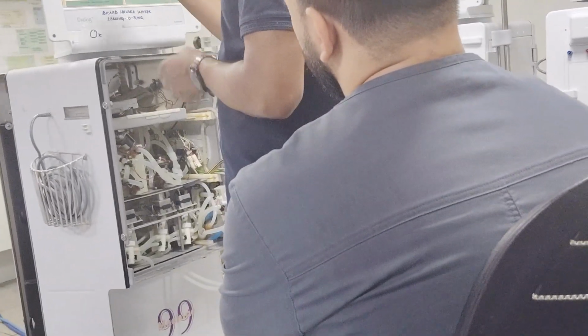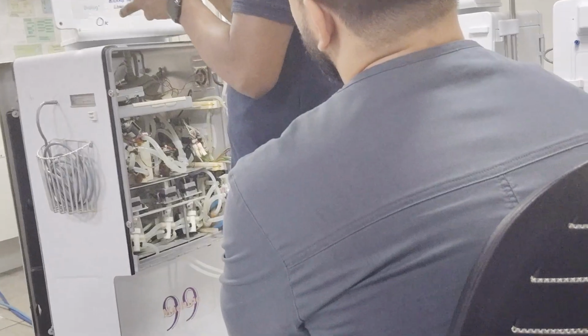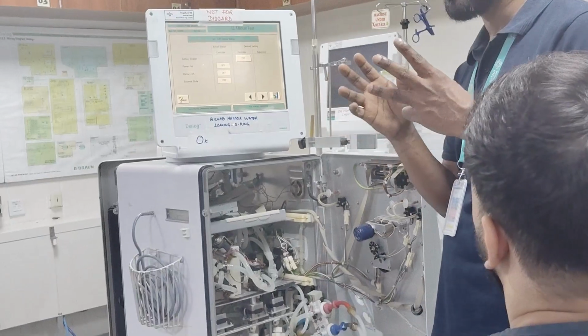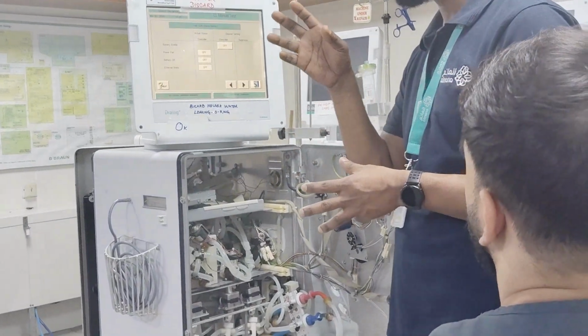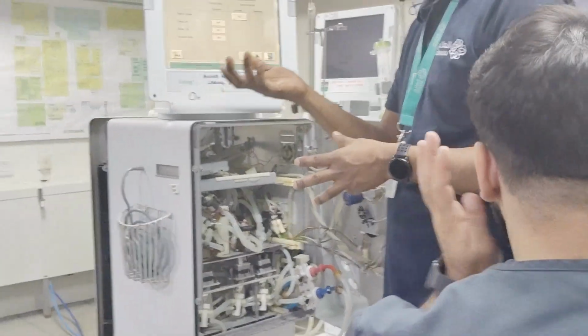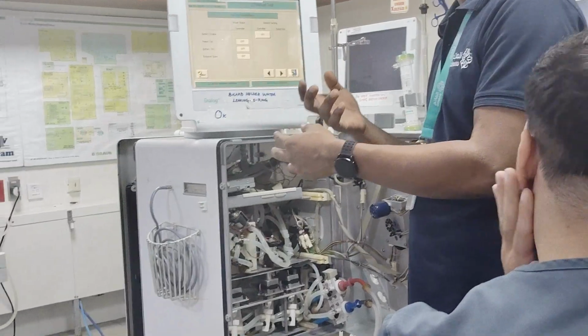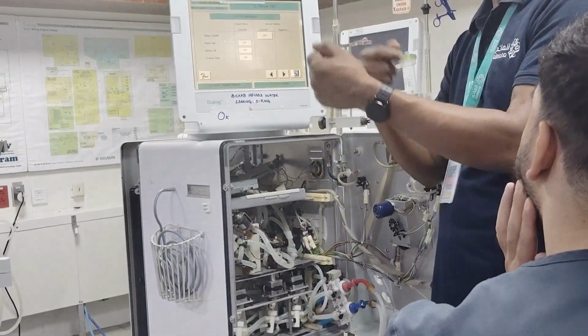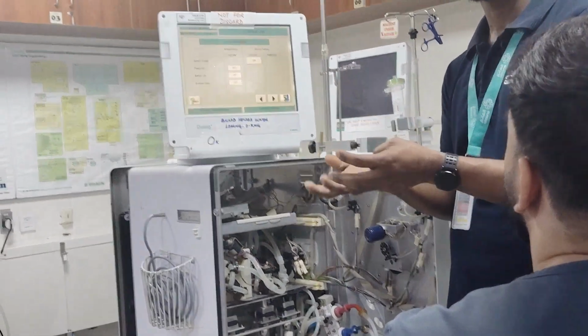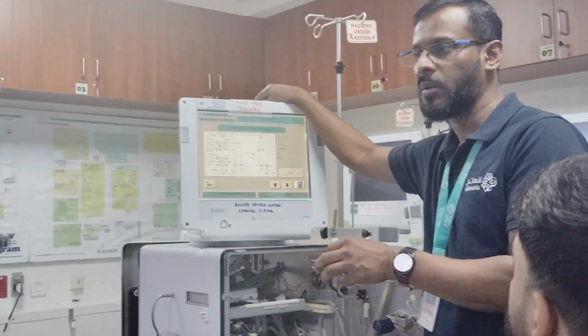After removing the plug, we can run the machine for hardly 20 minutes. We can run with the battery, which they will use during any power shutdown. So if the patients are running in the machine and there is a power shutdown, the battery will start up the machine. In 10 to 15 minutes, they can return the blood. By the time they return the blood, people will get the power back in the machines.